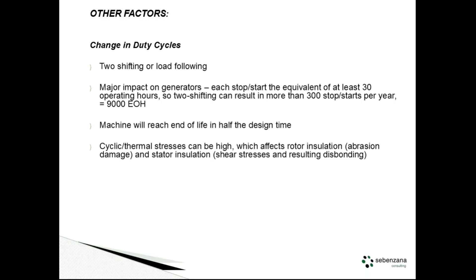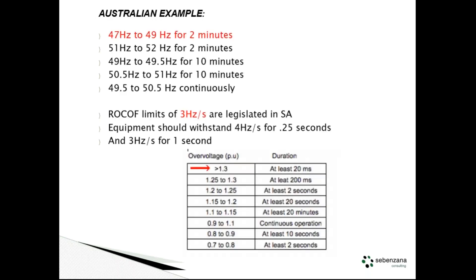Briefly, an example from the South Australian network: we did some work for them on synchronous condensers. They've shut down a lot of their coal-fired stations over the past few years and are running mainly on wind and solar — I think 54% of their generation capacity was recently from rooftop PV. They've got a really unstable grid — they've managed to trip the whole network at least once if not twice over the last couple of years. So they're putting about 600 MVA of synchronous condensers to cope with that. The requirement for the synchronous condensers is to handle 47 to 53 hertz, with 47 hertz for up to two minutes, a rate of change of frequency of 3 hertz per second, and up to 1.3 per unit over-voltage. This is not a nice-to-have — this is what the grid conditions are in South Australia right now.